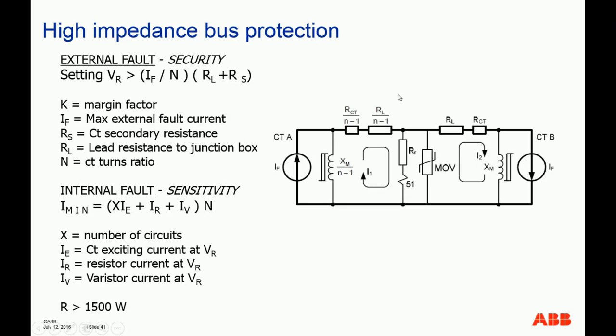So what happens is, when you have a big resistor here, all your CTs contribute current into the circuit. However, because of the external fault, let's imagine this CT is completely saturated. That's how we usually estimate the settings for the high impedance bus protection. If you have a CT completely saturated here, normally we wouldn't have any current here, because all the current from CTB will go through the excitation branch, and that will cause misoperation. However, the way the high impedance relay works is that this resistance, because it's big, will force the same current into that branch.